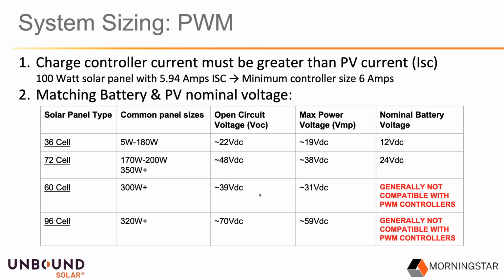It almost seems as though the 24 volt panel, the nominal panel, runs at about 48 volts. It seems counterintuitive that a 24 volt panel would work at 38 to 48 volts. Think a little bit about how the panel is going to work in the real world. The open circuit voltage is only going to be experienced in the morning when the system is starting up, and then once the charger actually starts, that voltage drops down to max power. So when your system's actually charging, we're using max power voltage numbers. The only thing we use open circuit voltage numbers for is really to make sure we don't go over voltage. We use that in design, but the panel's not really doing work at open circuit. So that's why we use the VMP if you're thinking about what the panel produces when it's charging.